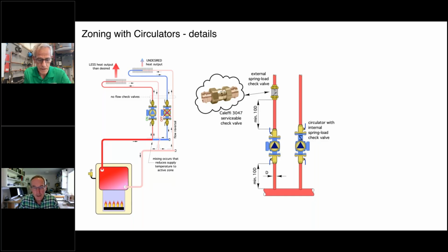Yeah, and Hot Rod, another thing, and you taught me about this. One of the things that can happen when you have a circulator in a pipe with upward flow, as you're commissioning the system, if you get some air bubbles trapped down here in the impeller, it is possible that the circulator can't clear itself, because that check valve does have a forward opening resistance, maybe about half a PSI. What will end up happening is you'll get this mixture of air bubbles and water around the impeller, and the circulator simply can't grab the water and clear itself of that air. Whereas if you put the check valve up here, those air bubbles can rise up out of that volute. And now the circulator will be able to grab the water and clear itself out. So that's another advantage of using a separate check valve compared to just the internal check valves in the circulator.